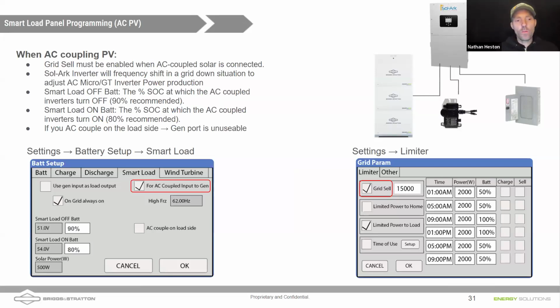Now, notice that the off value has switched. Notice that the off value for batteries is when you go above 90%, it turns off the AC coupled solar. And then when you drop down below 80%, it'll turn it back on. Why do we want to turn off the AC coupled solar in a grid down situation, Daniel, when the batteries are above 90%? We want to be able to shut the AC coupled solar off before the batteries are full. It's not necessarily an instantaneous thing, and if we get it too close, there's a chance you could damage the batteries by not turning off that AC coupled solar.